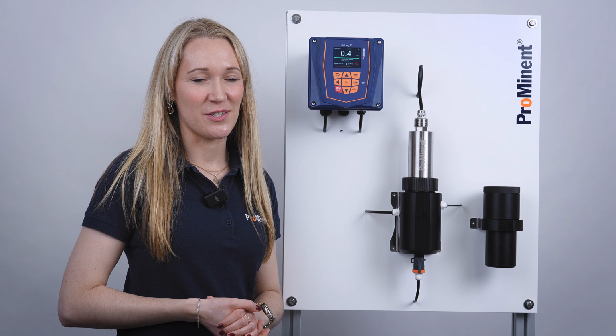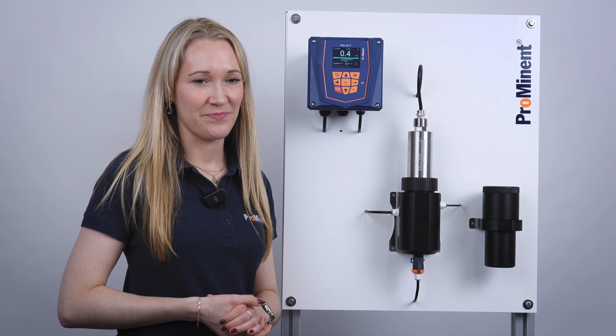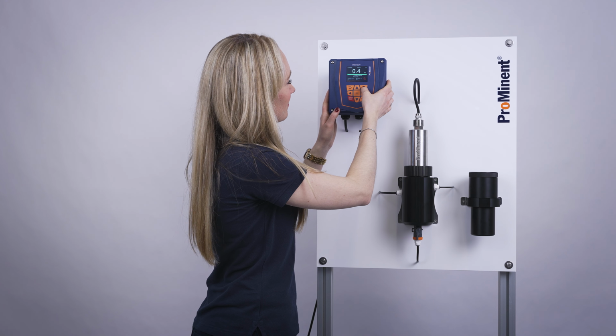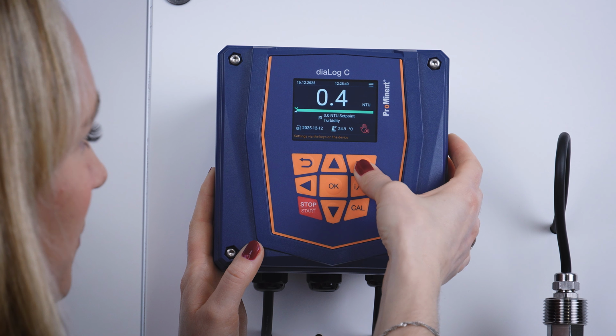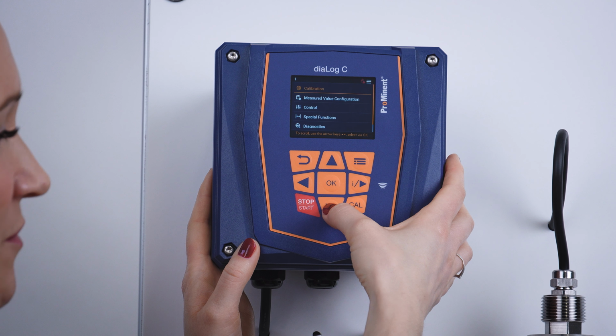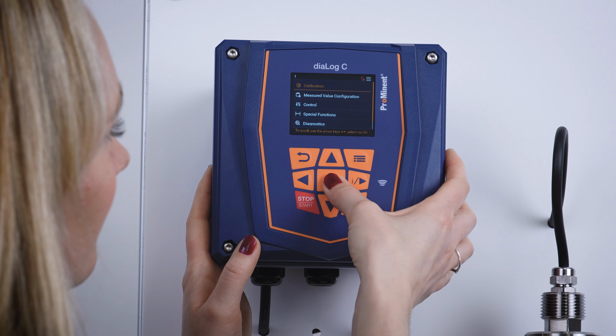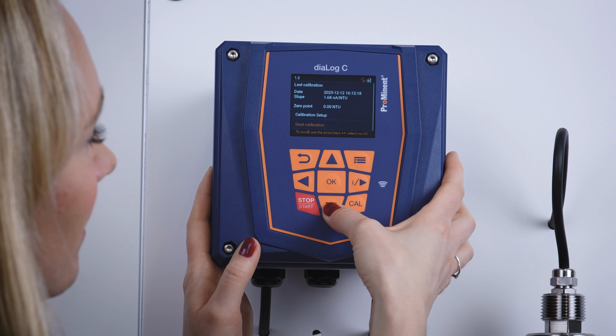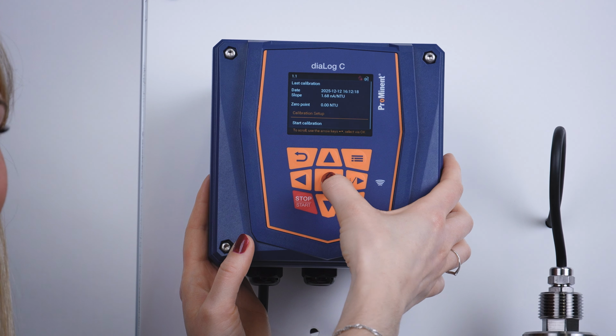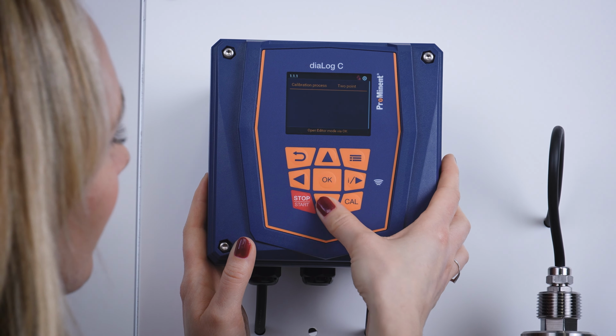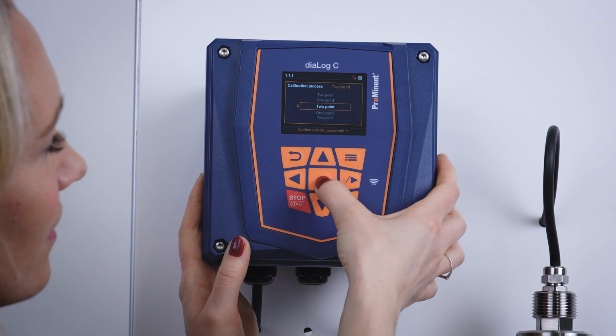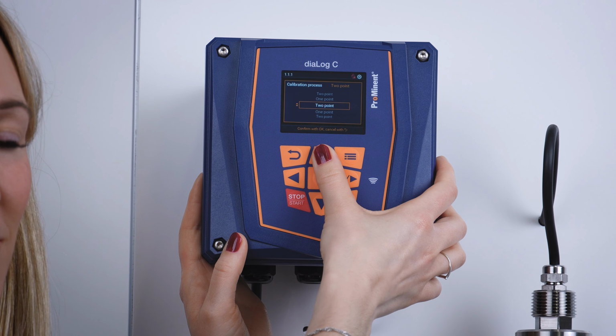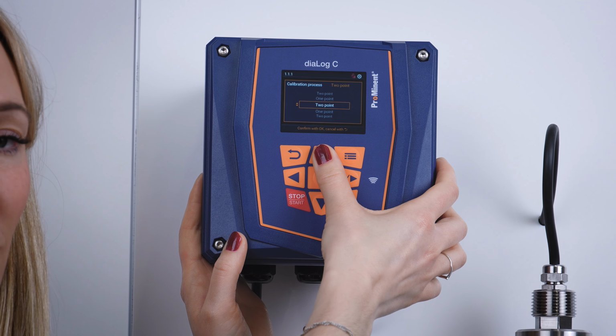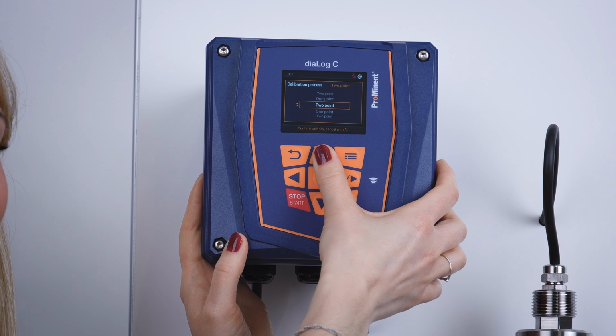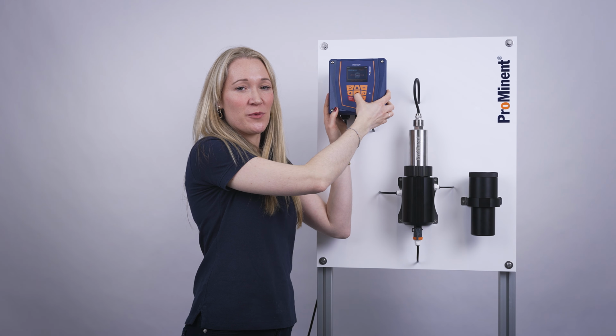To start the calibration, we go into the controller menu. In the menu, you find the point calibration. And there you find the calibration setup. Here you can choose between two different calibrations. You can either perform a 1-point or a 2-point calibration. In this video today, you will perform a 2-point calibration.